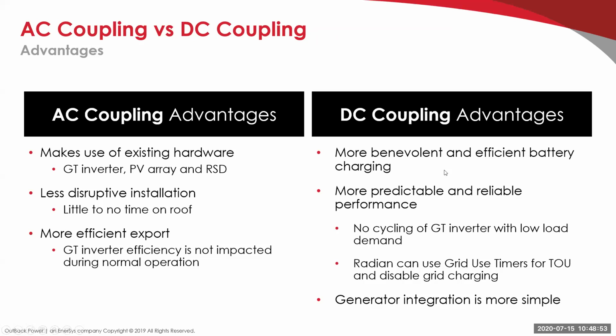When you're DC coupling, it's more predictable and reliable. With DC coupling, the Radian can use time of use, and we can guarantee it will never charge from the grid if that's a requirement of some utility program. So it is more predictable in that regard.